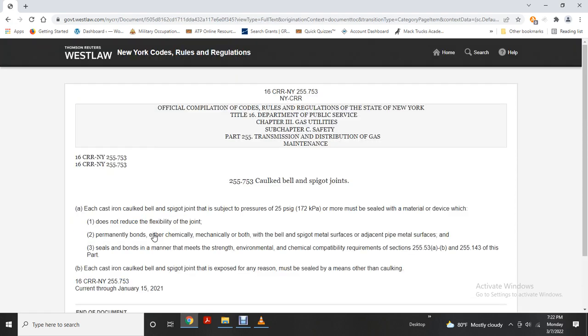Alright, caulked bell and spigot joints. Each cast iron caulked bell and spigot joint that is subject to a pressure of 25 psi gauge or more must be sealed with a material or device which, if it does not reduce flexibility of the joint, permanently bonds, either chemically, mechanically, or both, with the bell and spigot and the adjacent pipe surface, and which meets the strength and environmental chemical compatibility requirements of sections 255.53 (a) and (b) and 255.143 of this part. Each cast iron caulked bell and spigot joint that is exposed for any reason must be sealed by means other than caulking.